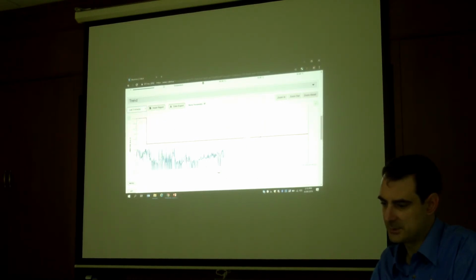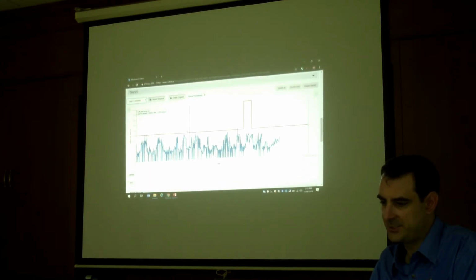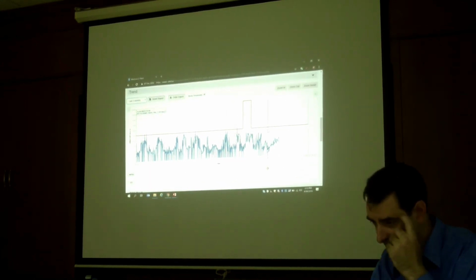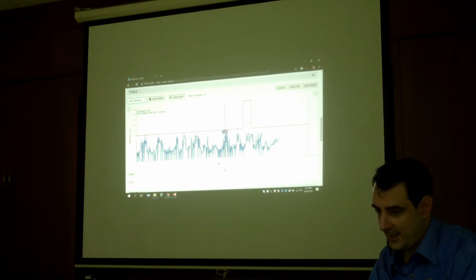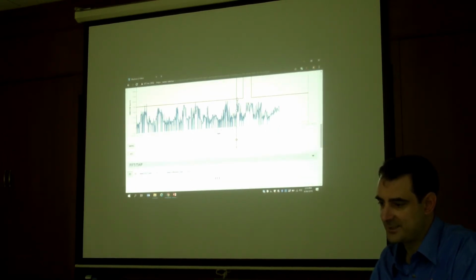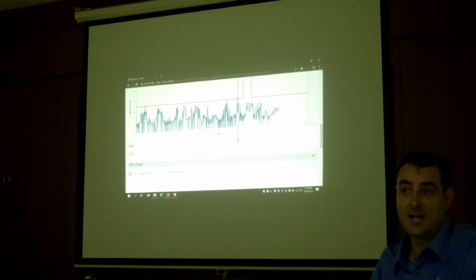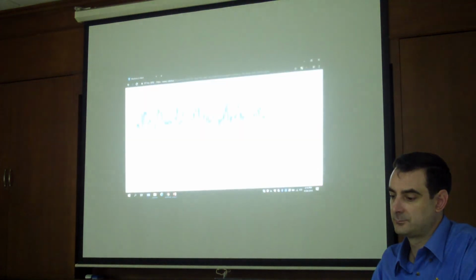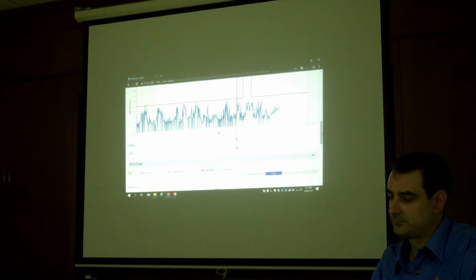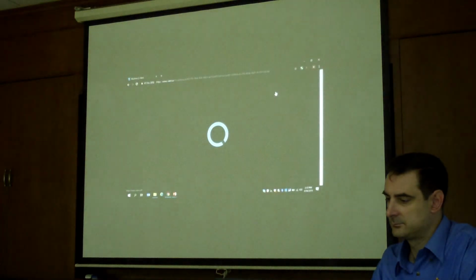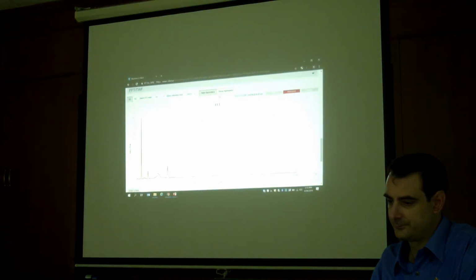If I go to the last 3 months, this shows the alarm levels, where they've been sitting. And we've been crossing this at certain points. Every time we cross, we get this additional data point, but see down here, this triangle, this is the alarm triggered vibration spectrum. So if we want to look at that, we click on it. And it will scroll down. And it will show you the vibration spectrum.